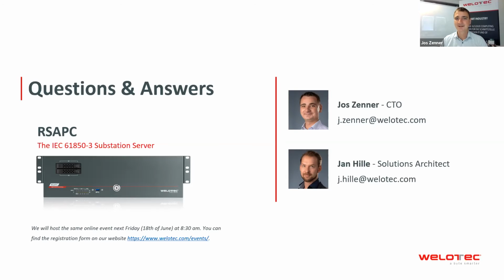Definitely yes. The reason behind this is that it's independent from the software. So you can run a gateway software that is then able to speak those different protocols. For example, if you need to convert IEC 61850 protocol into DNP3, you can look at the market, and there are a lot of vendors for this. The global players have it within their substation automation systems, but there are also other companies like Kalkitech, for example. There's a company called iGrid.